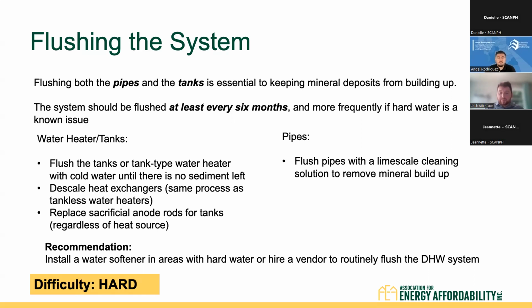And then I think we have a question here: what is the recommended pH level for water? Hard water is measured in grains of calcium and bicarbonate, and that testing strip is going to tell you that. Your manufacturer of the heat pump is going to give you a range of what they are okay with in terms of how hard the water is. So if you're installing a heat pump water heater that requires a certain grain level and you're exceeding that, you should consider having a water softener, or you should be really aggressive on flushing the system and ensuring that you aren't going to have hard water issues. And just work with your manufacturer or the contractor that is installing the equipment to make sure that you're following the manufacturer requirements and guidelines. Next slide here.